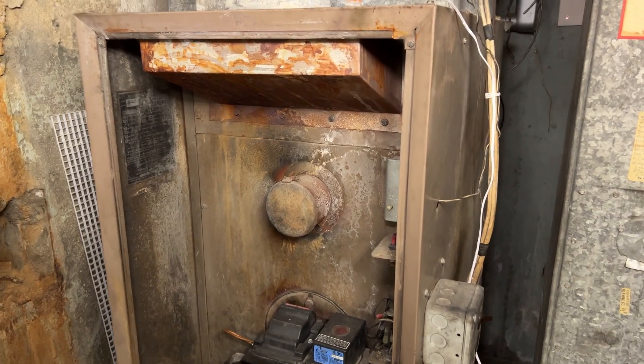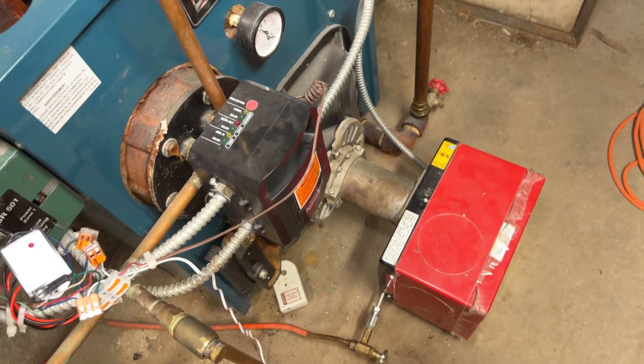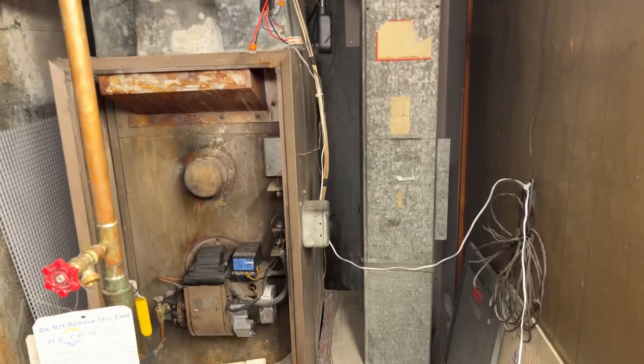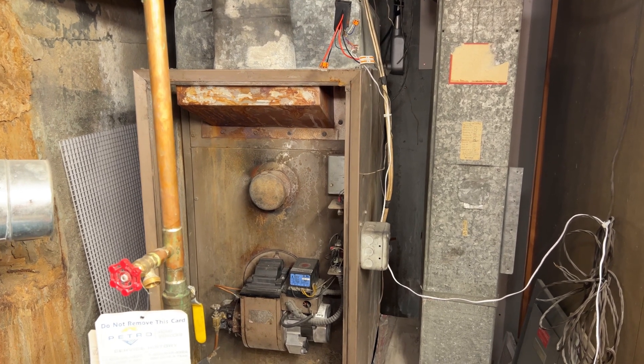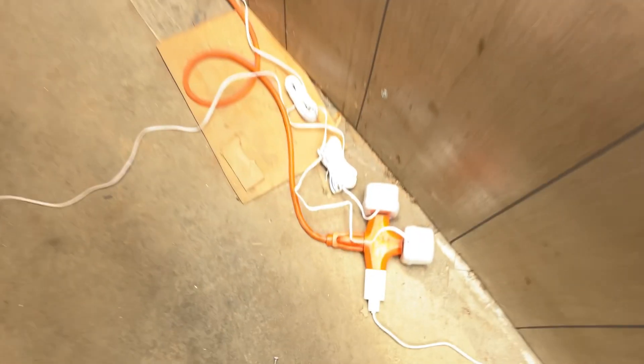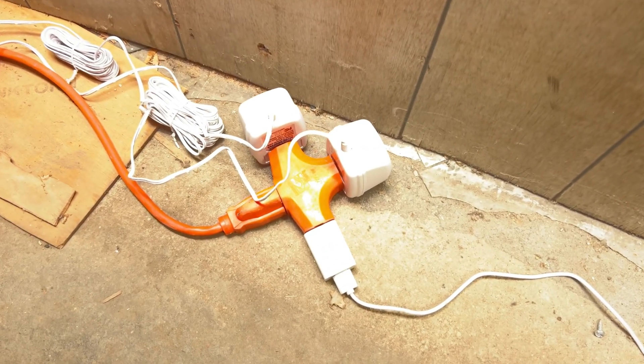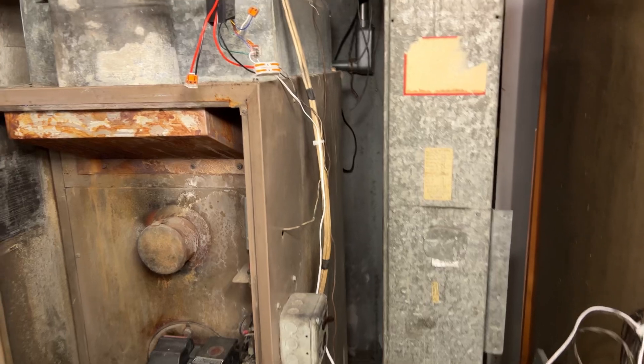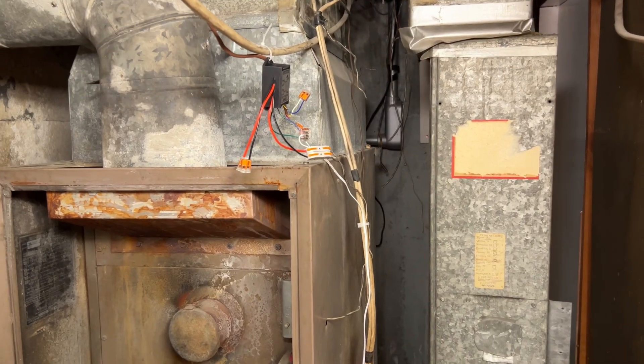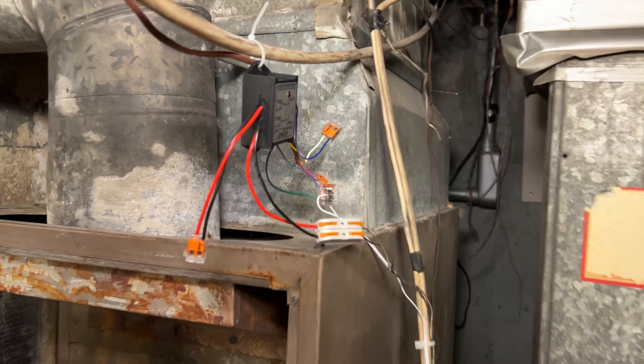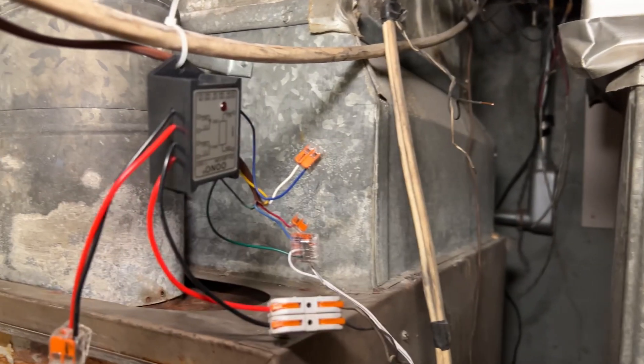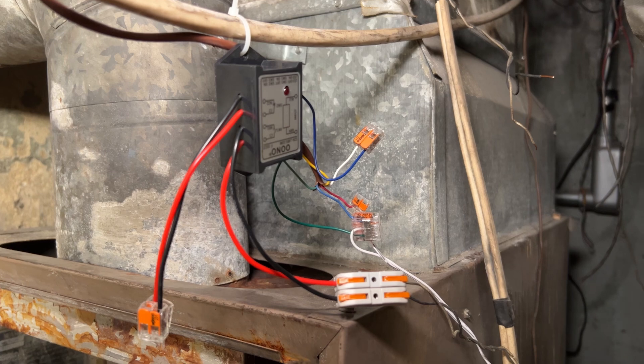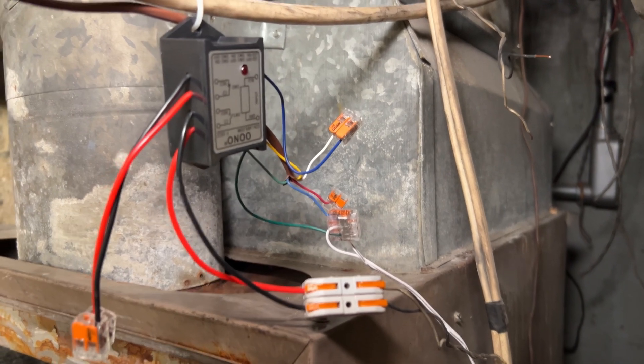In fact, the furnace which is really old has two wires and our boiler which is pretty new also has two wires on this zone. We're using the same solution for both of these in order to use a smart thermostat, and that solution is to use these 24 volt AC power supplies. These are external 24 volt AC power supplies and really all they're doing is powering the smart thermostats, because the smart thermostats need 24 volts and they need a common wire and so we're providing that.